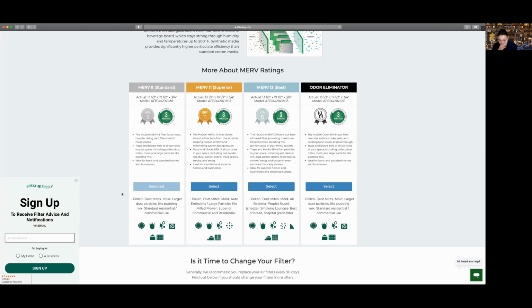The downside with the higher MERV is that as you increase your efficiency rating, the filter lets less things through. So there's going to be less airflow, and you might impede airflow. If you currently don't have enough airflow, you might not be able to use the MERV 13. You might only be able to use MERV 8 because you don't have enough supply and return air. When you use a higher MERV system, it will impede airflow. If you don't have issues with airflow, then definitely go with the higher MERV 13.